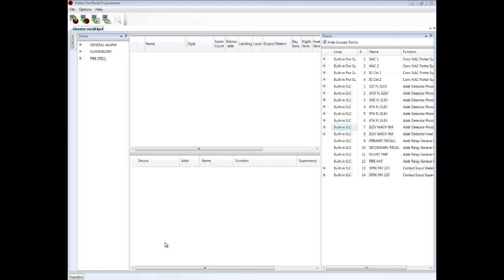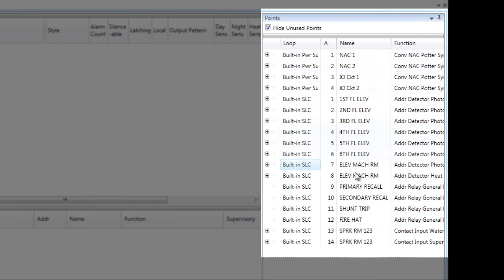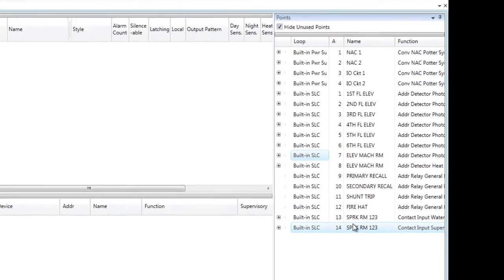Now taking a look at the programming. To demonstrate programming elevator recall, I'm using a PFC 6075 program. I've already uploaded the program and customized the messages of all my devices. I have four notification circuits. I have smokes in the elevator lobbies, first through sixth floor. I have a smoke detector in the elevator machine room, a heat detector in the elevator machine room, my four relays — primary, secondary, shunt trip, and fire hat — as well as one sprinkler zone with the water flow and supervisory.